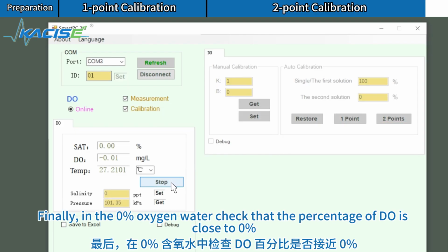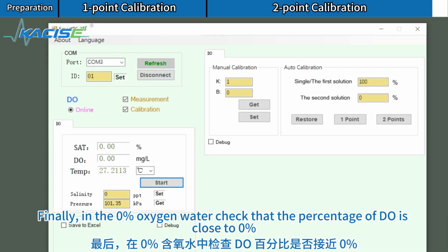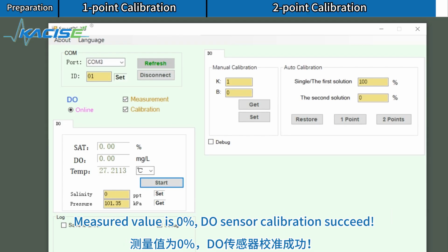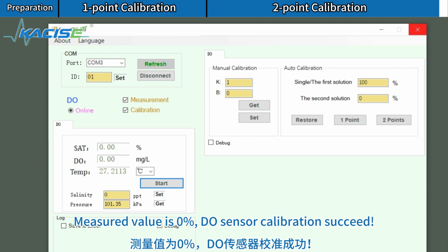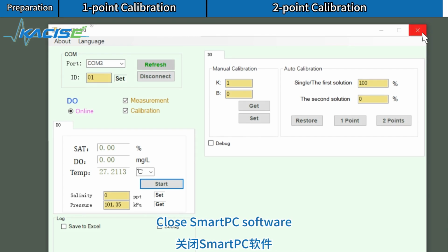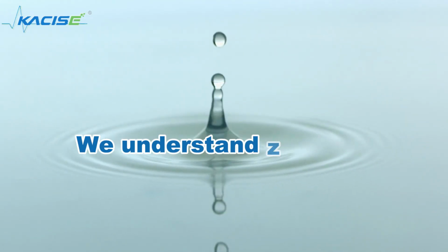Finally, in the 0% oxygen water, check that the percentage of DO is close to 0%. Measured value is 0%. DO sensor calibration succeed. Close the Smart PC software. We understand your needs.